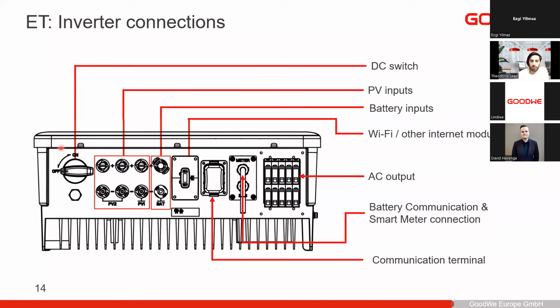To go through the layout on the bottom side of the inverter, starting from the left, you see the DC switch, just an on and off. Then we have the PV inputs with PV, this is the first MPPT and the second MPPT. On the European models, we only have one input per MPPT, so one of these will be blocked. You can only use one string input, even in the second MPPT.